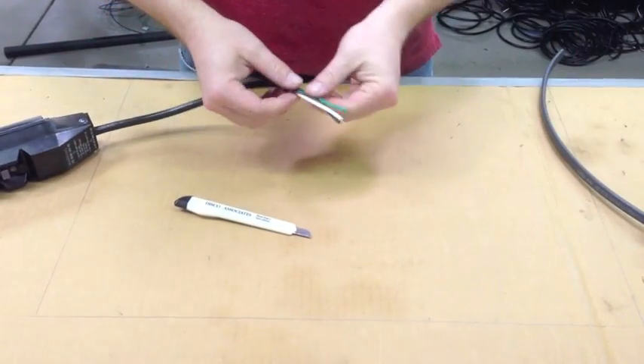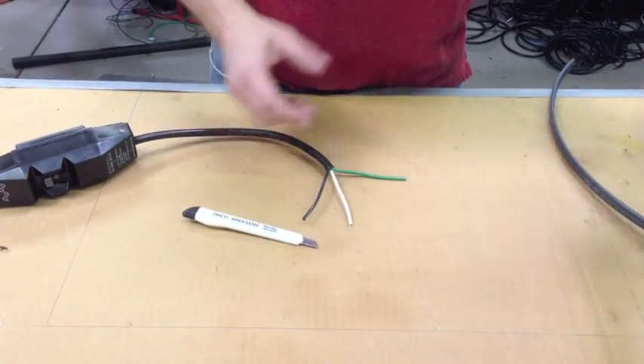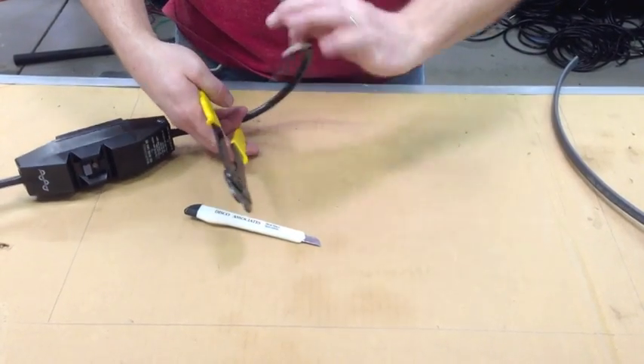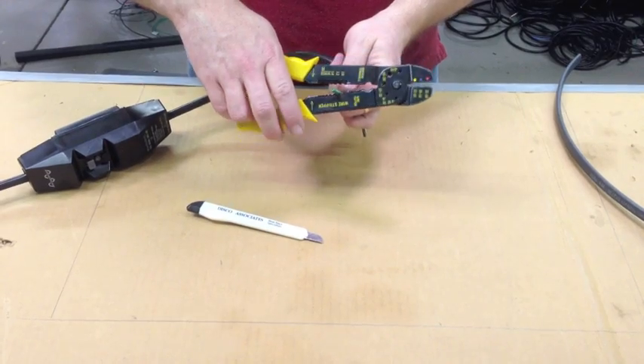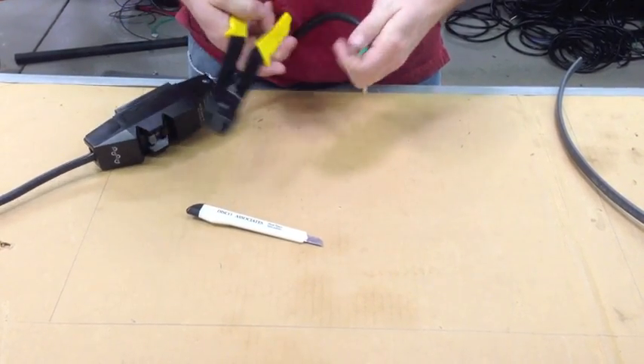Remove 4 inches of the insulation on the SO cord. Make sure that there is about 4 inches worth of ground wire left. Now remove all the insulation on the ground wire back to the SO cord.